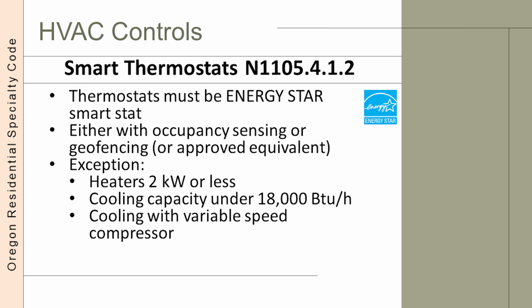And finally, per a statewide alternate method, any cooling system with a variable speed compressor where the manufacturer requires their own thermostat is also exempted. Because the control of these compressors relies on special ramping up and down of the compressor capacity, as well as defrost control when the system is a heat pump. Using an Energy Star thermostat from a different manufacturer could void warranties or damage the equipment. So this is one exception for where an Energy Star thermostat is not mandated, and it is required to be approved by the building official.